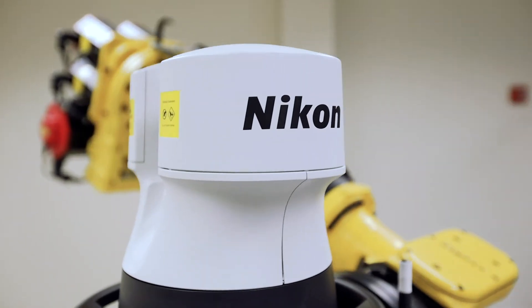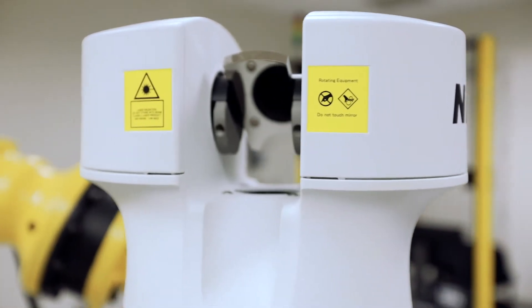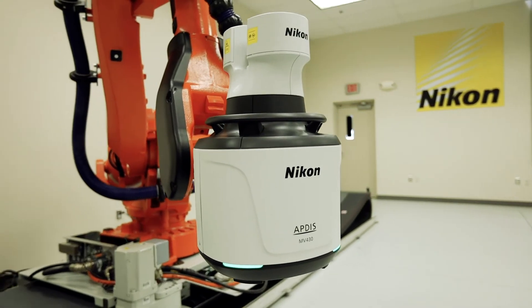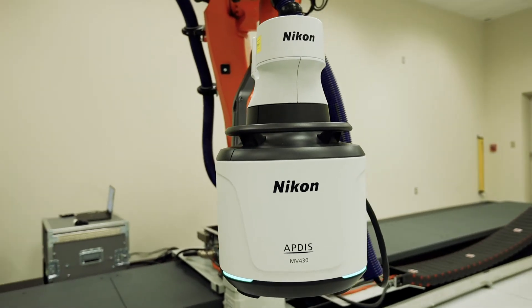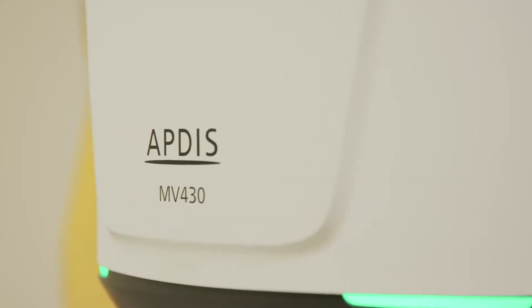Nikon APDIS is a highly accurate non-contact three-dimensional measurement system for measuring large-scale objects such as airplanes and automobiles, to precisions down to a thousandth of an inch. What's different about our laser radar is we're the only one on the market that measures frequency shifts in the measurements versus time of flight. So now we are talking micron resolution level, versus other products which are at millimeter resolution level.